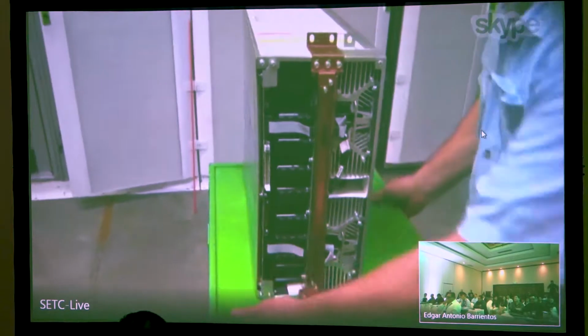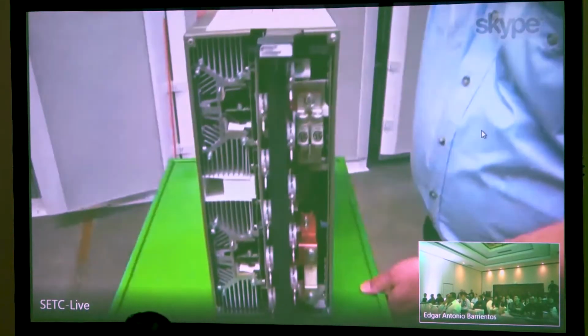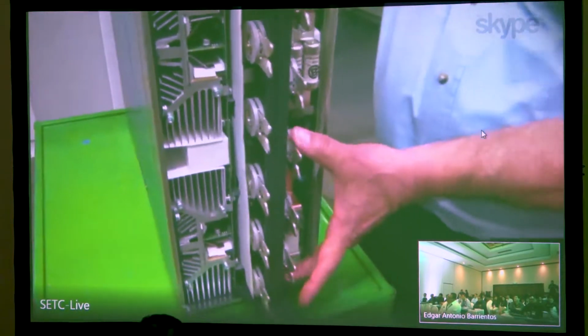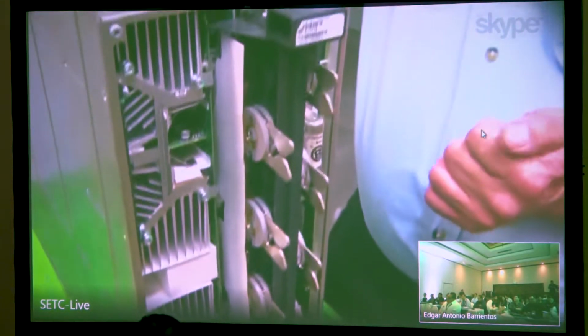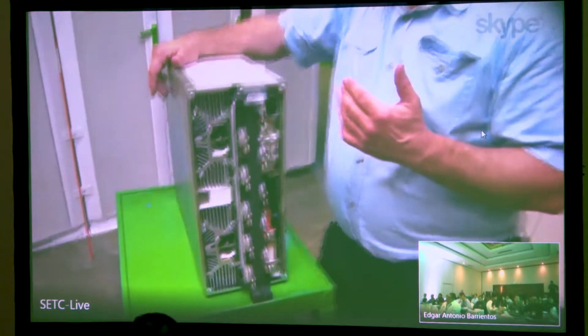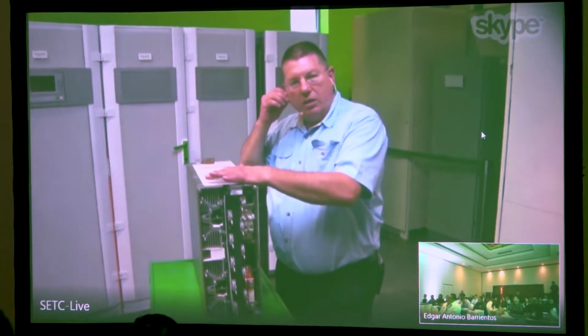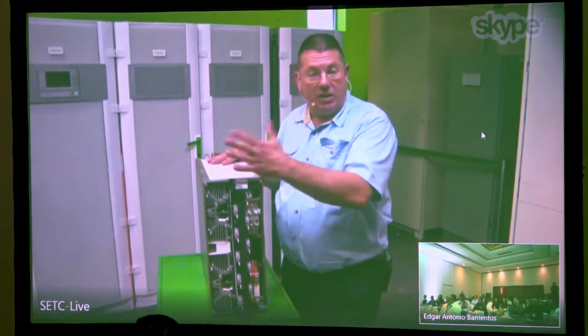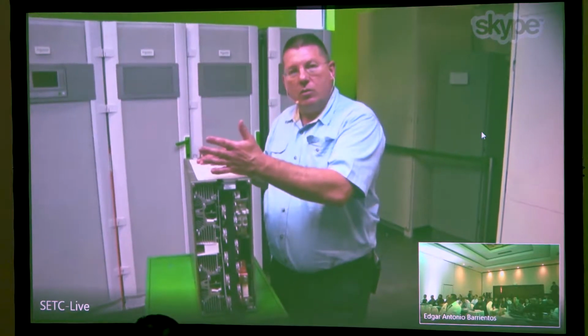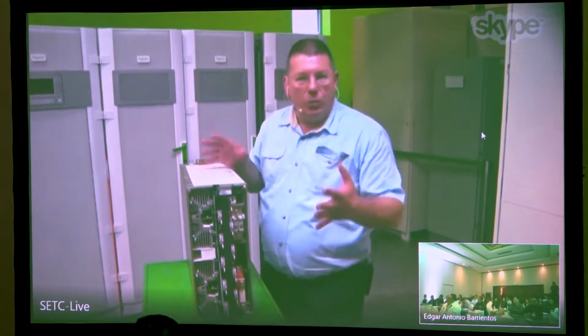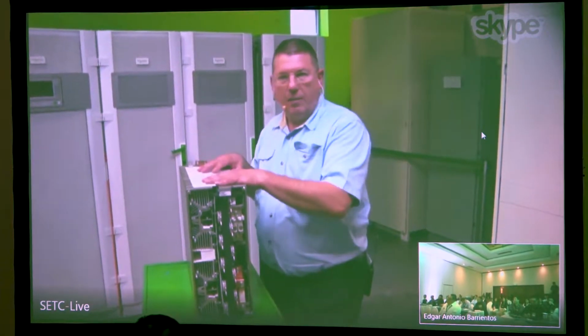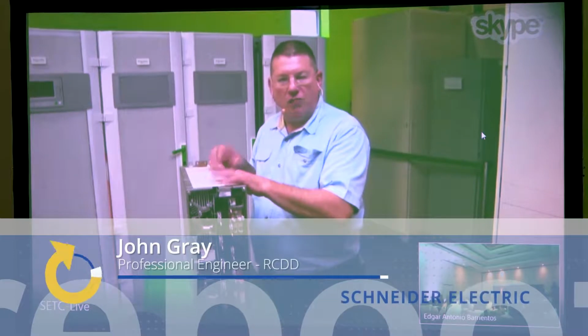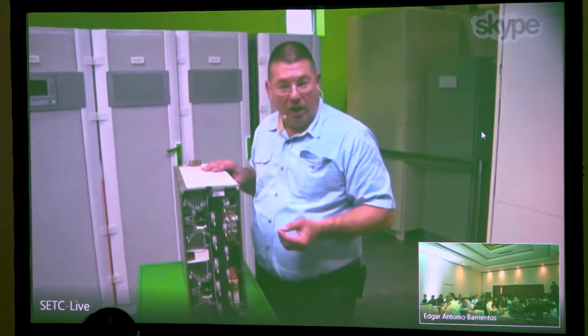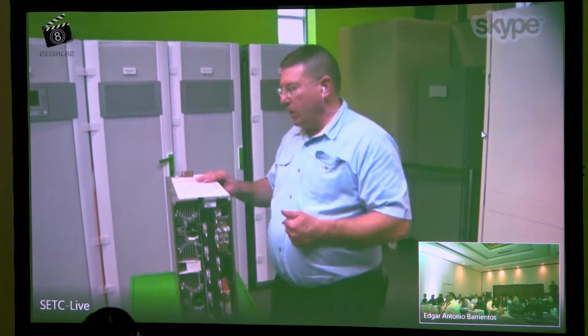I'm going to spin it so you can see the back as well. And this is where the power block ties into the backplane riser in the power cabinet. Okay, so very easy to install. It's roughly about a 20-25 minute process to replace one of these at that revitalization time frame if everything else is set up right. So the UPS is already in a de-energized maintenance bypass condition. So pretty easy, pretty straightforward to do this. And then just bringing it up online and testing and configuring is all done by the field service engineer and the tuner that they have. Okay?